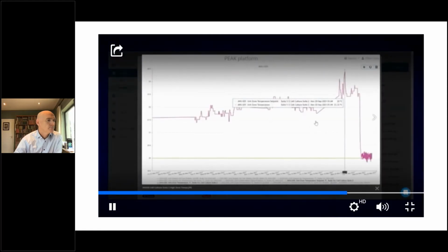The first one was to check the chill water valve and coil operation, and if that was all good, check the control logic, and if that was all good, then have a look at the various sensors that feed into the control. What was found on the first check was that the strainer was blocked, and in turn there was no cooling getting to the coil, which meant the supply temperature set point could not be achieved. The impact was that the validated space itself, which had a set point of 20 degrees, was rising to close to 24 degrees. And at 24 degrees, production would have to be stopped in that area, and there could be potential compliance issues. What did happen was we got to the problem before it became a compliance issue. The zone got back into control and the issue was resolved.